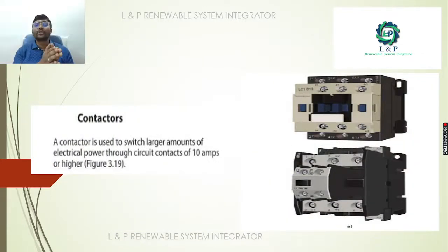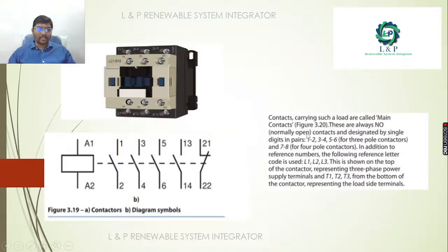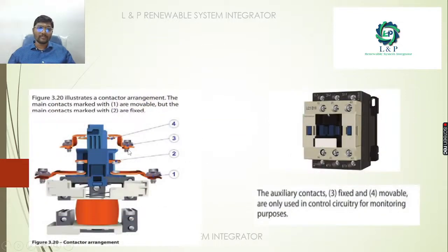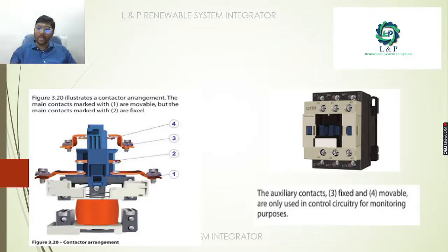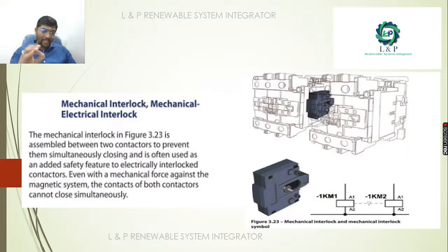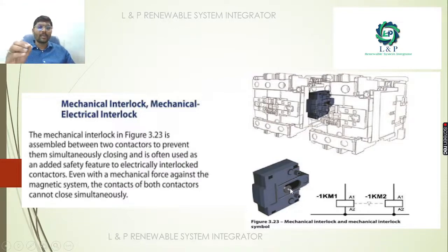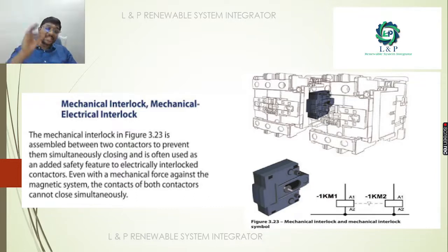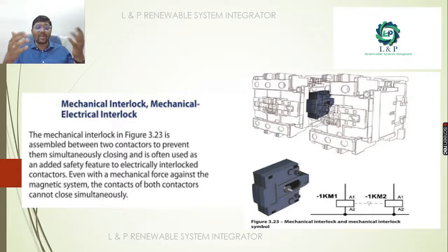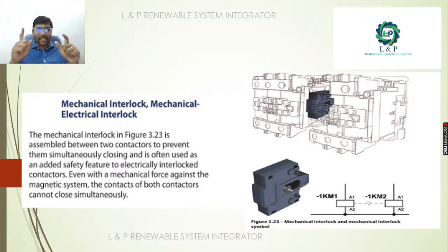A contactor is used to switch larger amounts of electric power — typically 10 amps or higher. This is a real-time photo and the contactor symbol. The auxiliary contactor has fixed and movable parts and is mostly used for controlling circuitry and monitoring. A mechanical interlock assembled between two contactors prevents them from simultaneously closing, and is used as an additional safety feature to electrically interlock contactors — for instance, to prevent two contactors that should not operate simultaneously from doing so due to any false or reverse signal.